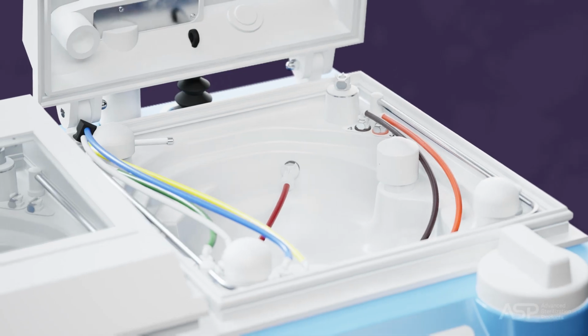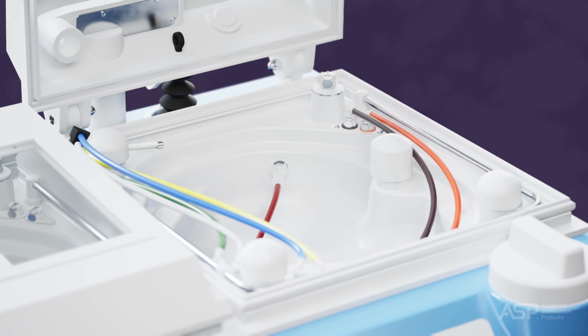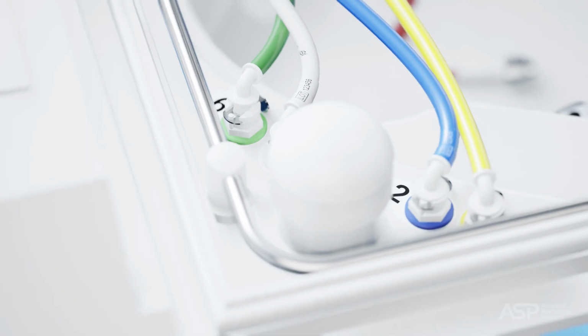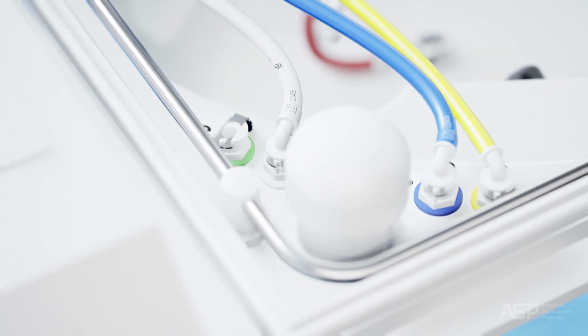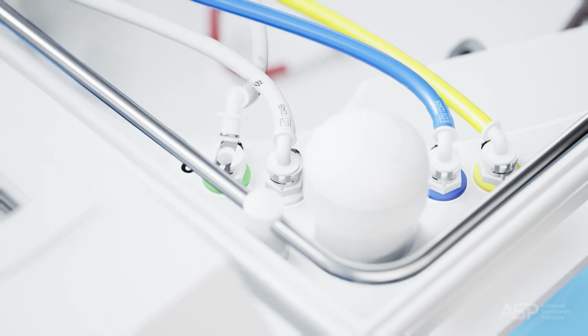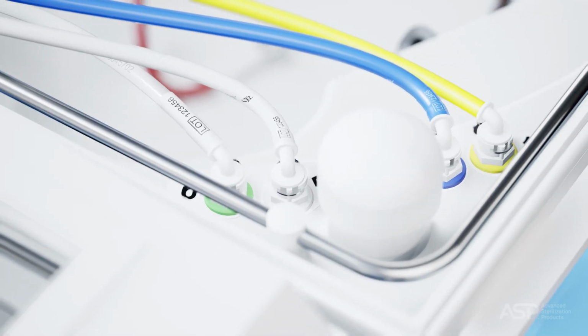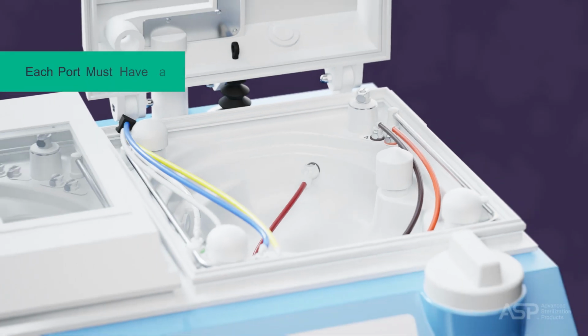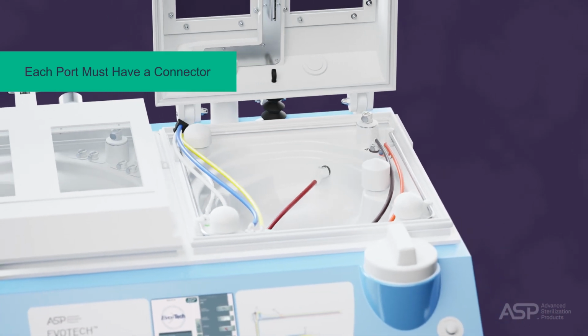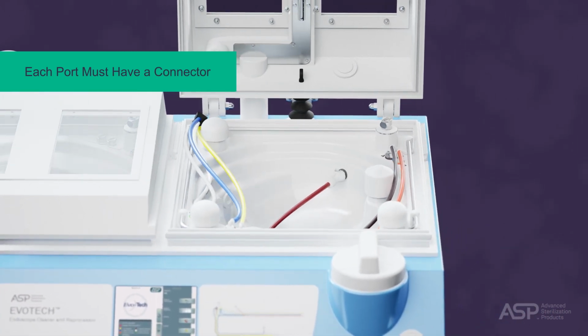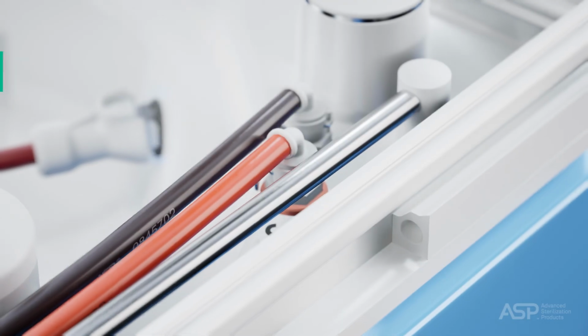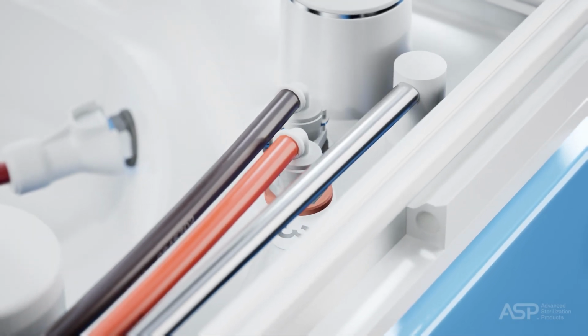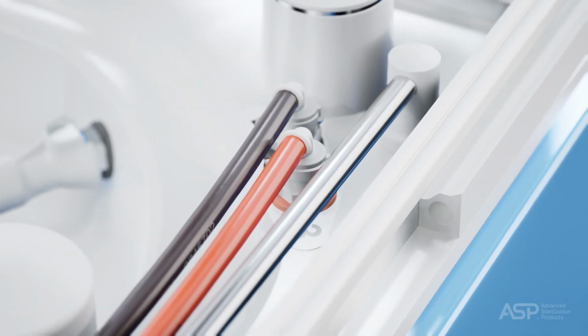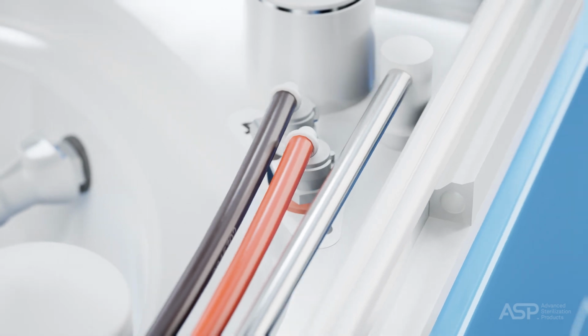To run a cycle, all 6 basin ports must have a connector in place. When a diagram does not indicate that a colored connector is needed, a clear connector will be required to connect the endoscope to the basin. You must have a connector in each port to ensure that contaminants are not trapped in the tubing. While placing the connectors, inspect them for wear and tear and replace them if you notice any tears, cracks, or damage.